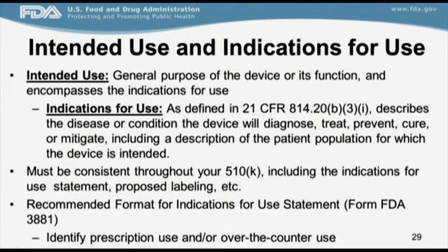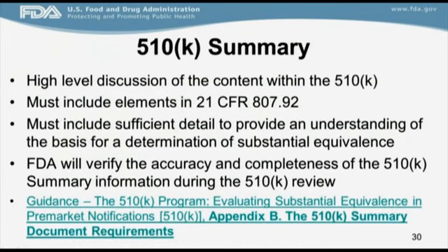There is a recommended format for your indications for use statement. Please refer to Form FDA 3881. And when you submit that form, make sure that you identify whether or not your product is considered prescription use or over-the-counter. The next aspect of your content of your 510K should be your 510K summary.